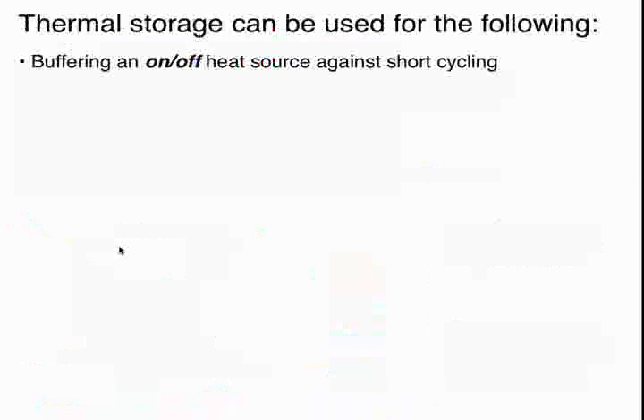So what do we use thermal storage for? There's quite a few things. We're going to look at buffering boilers, again, short cycling. Short cycling is this idea that the heat source, be it a boiler or a heat pump, is on for an unacceptably short period of time. Maybe it's on for a minute, minute and a half, 2 minutes, and then it's off.